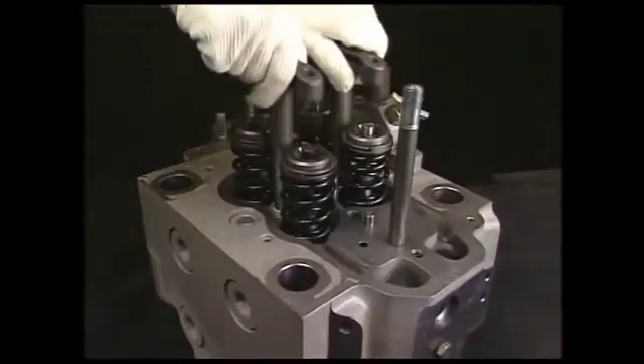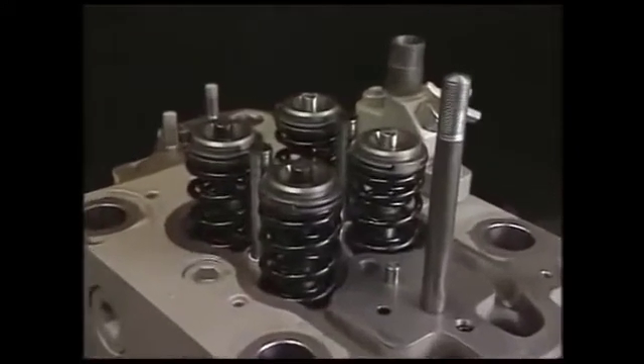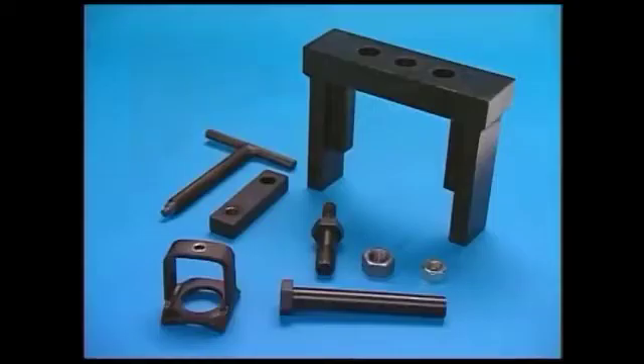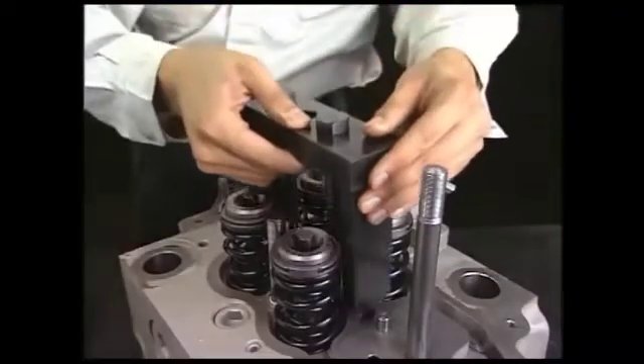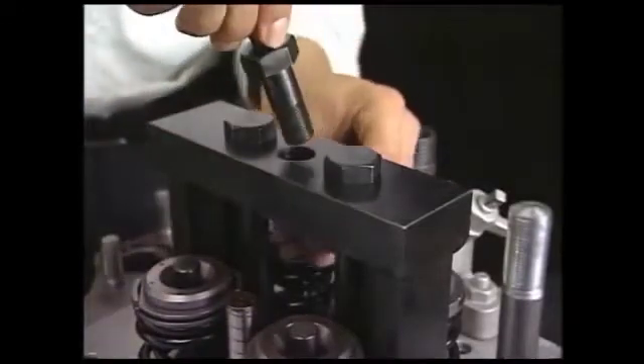Remove the suction and exhaust valve supporter from the detached cylinder head. To remove the suction and exhaust valves, remove the valve rotators, cotters, and valve springs. Prepare the exclusive tools for removing. Firstly, fix the lifting tool of cylinder head with the tightening bolts of fuel valve by the drawing of tool B. Turn the handle clockwise after attaching the exclusive tool.